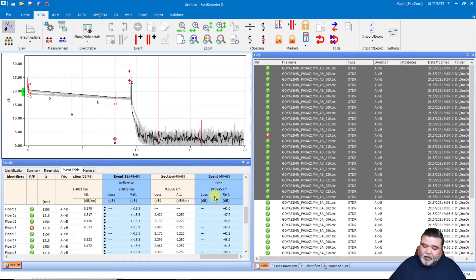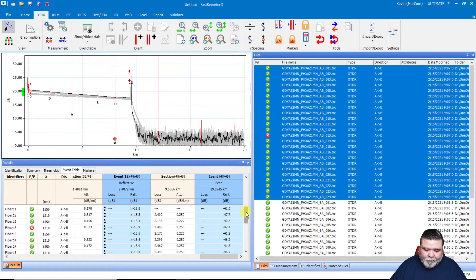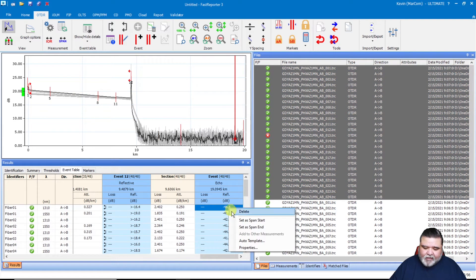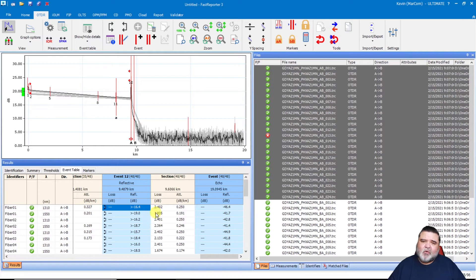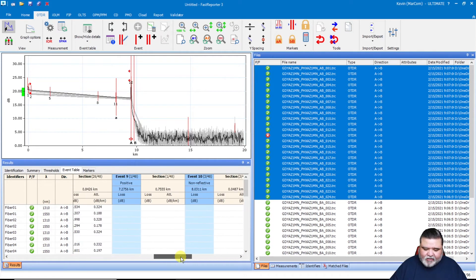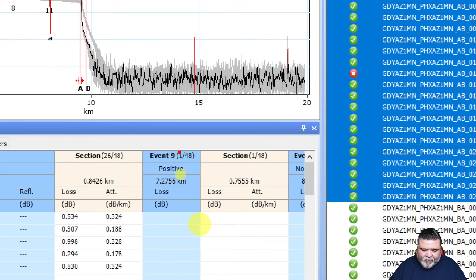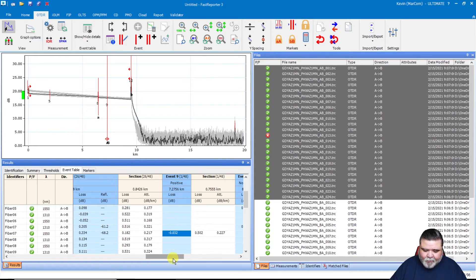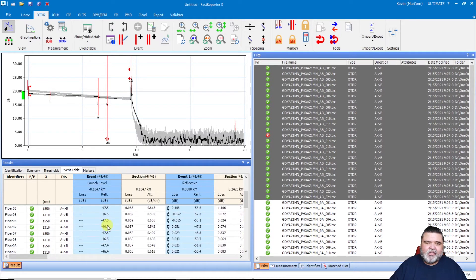I go to the end to see if it all ends at the same location. The end of fiber or end of span is over here, but we still have data beyond it — this is caused by ghosting. One of the traces ghosted pretty badly. This is a real trace I borrowed from a customer — I just took all the identifying information off because it was a good example. I have 48 of 48 all the way down. If one of them was misplaced at the wrong location, I would need to move that span end marker. I'm going across checking and validating the data, noting a very low loss gainer on one fiber.